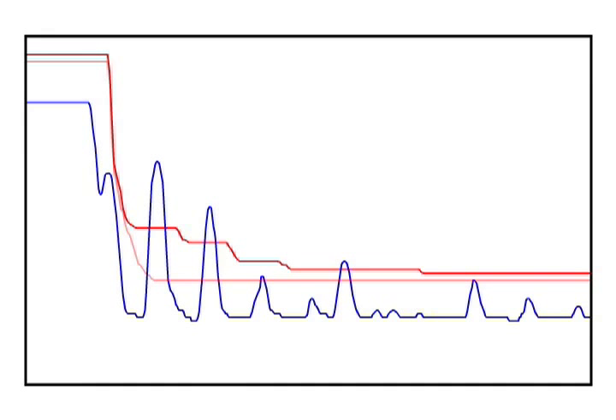With the dynamic TVT, we de-emphasize the influence of these false echoes and focus the device on the true material echo. The dynamic TVT curve is unique to Siemens ultrasonic and radar devices. None of our competitors have this feature.